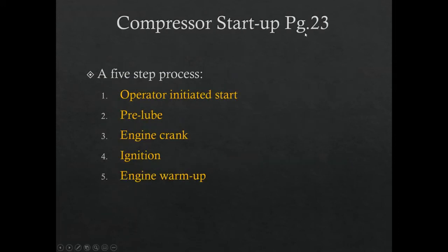Okay, so compressor startup for a reciprocating compressor is basically a five-step process. So operator initiates the start, aka press the start button. At that point, we'll get pre-lube in the compressor. So our lube skid will fire up. It'll start pumping oil into the compressor to get everything good. There will be a pressure switch attached to the pre-lube system.